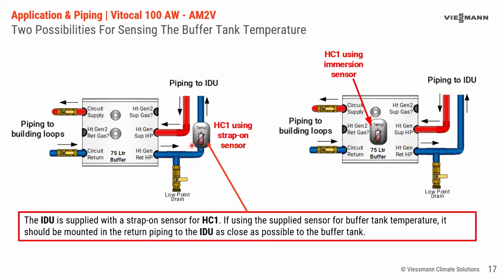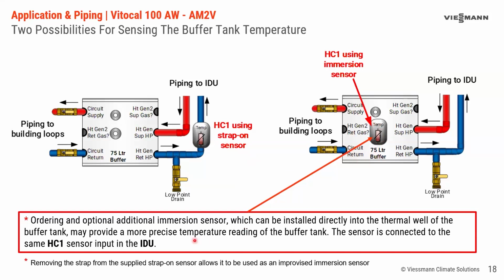So you have a couple of other options you could do here. You could use an immersion sensor, which is a sensor you could buy as an option. Our lab tech has done some testing on the strap-on sensor, and by nipping off the strap and putting it into the immersion well, this could become an immersion sensor using the sensor that comes with the heat pump. And if you'd rather have one more designed for immersion, there is the option of buying another immersion sensor and using it. So this is totally your choice. I know there are guys who are more familiar with the controls than other guys, and they might have a methodology that says this sensor does this with 360 degrees pickup with the strap-on sensors. We've done testing on it, and it doesn't seem to be a lot of difference, if any, between the two, but it's totally up to you how you want to do it. You can nip off the strap on the strap-on sensor, or you can buy the optional immersion sensor, and then it just fits right inside the well of this tank.